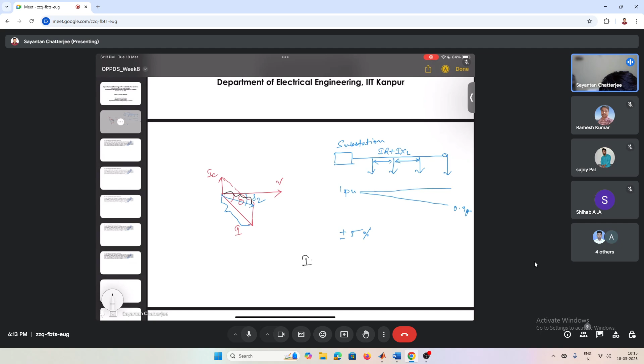So the drop, that is IR and IjXL, mostly the system would be inductive, since the loads, induction machines and all these things lead to this. Here it would be multiplied by IjXL. So ultimately, if this I value gets reduced, that would lead to a minimization in the total voltage drop.